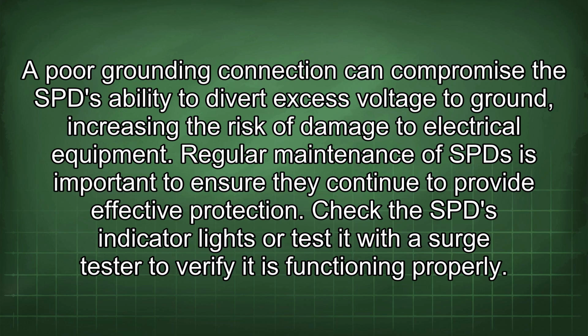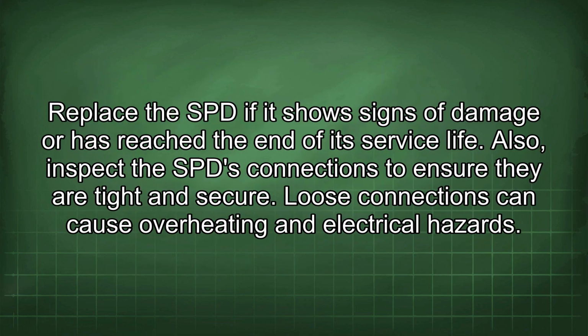Regular maintenance of SPD is important to ensure they continue to provide effective protection. Check the SPD indicator lights or test it with a surge tester to verify it is functioning properly. Replace the SPD if it shows signs of damage or has reached the end of its service life. Also inspect the SPD connections to ensure they are tight and secure. Loose connections can cause overheating and electrical hazards.